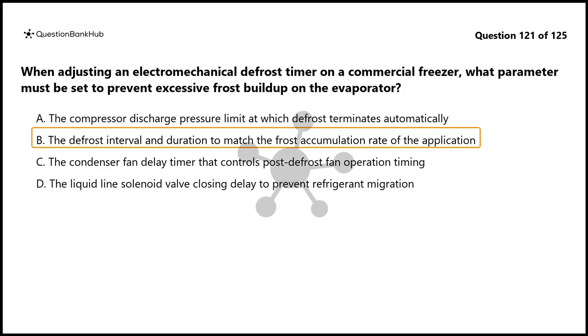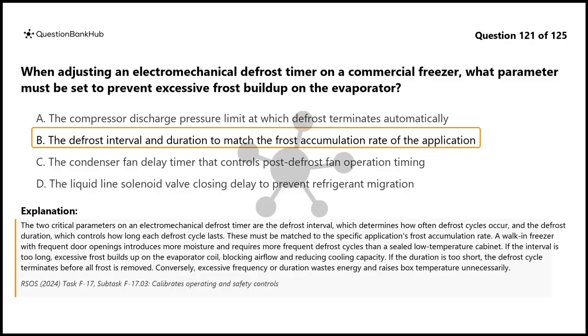The correct answer is B. The two critical parameters on an electromechanical defrost timer are the defrost interval, which determines how often defrost cycles occur, and the defrost duration, which controls how long each defrost cycle lasts. These must be matched to the specific application's frost accumulation rate.